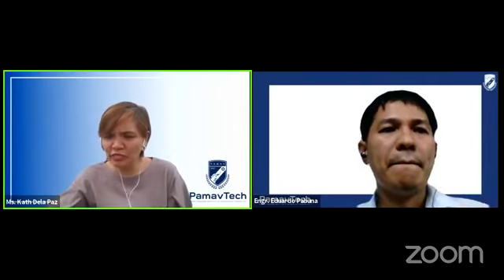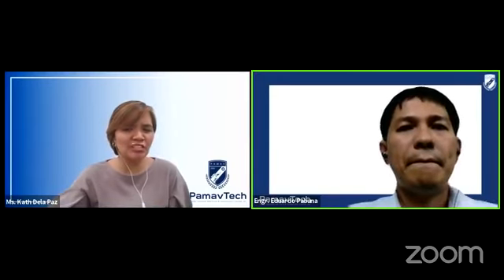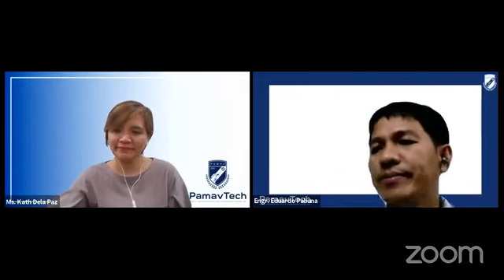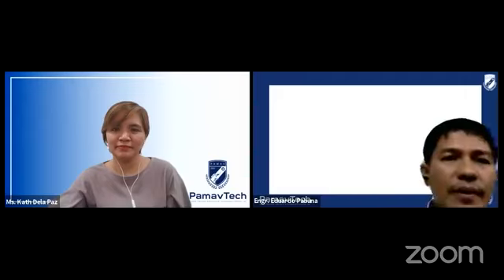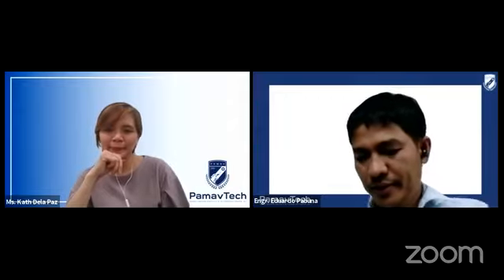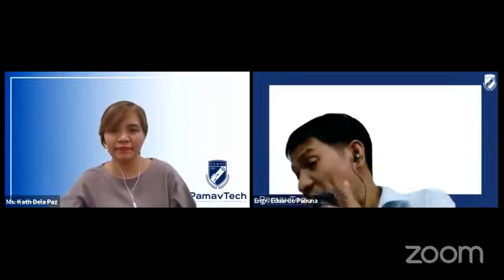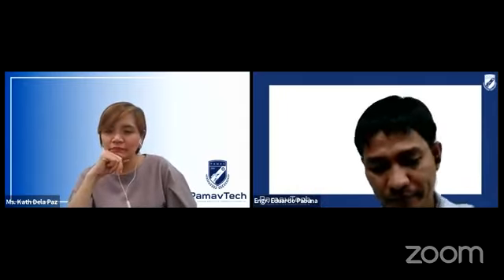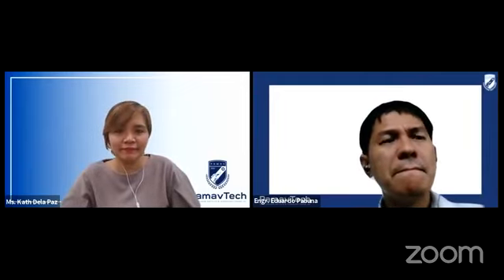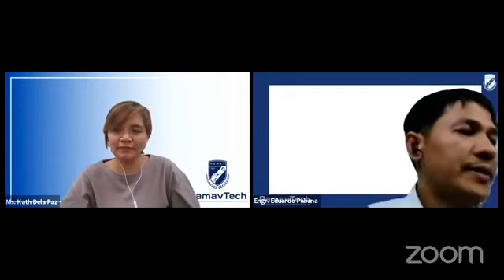All right, we have a follow-up question from Engineer Juniel. Can a series reactor also protect the system during voltage abnormalities, as you mentioned? The series reactor can protect your system from a sudden rise of current. If your voltage suddenly drops, your power is constant, so there is a sudden rise of current. That is why if you encounter voltage sags, there is a spike in the current, and the reactor can mitigate or counter that spike. So the reactor can protect the equipment. That's why some VFDs have the AC choke, or the reactors.